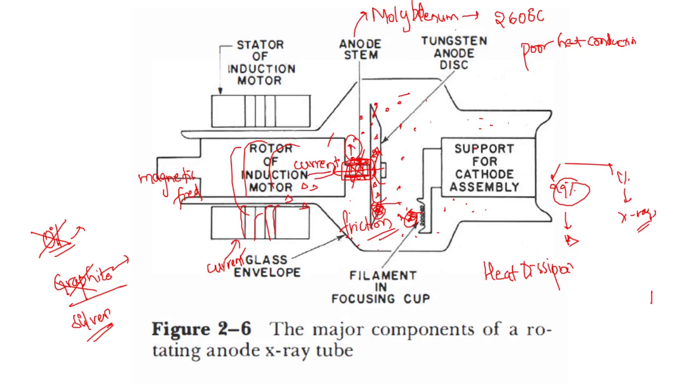So when the inertia of the tungsten load increases, it will take time for the tungsten to move before it is rotated. To prevent that, this anode stem is made as short as possible.